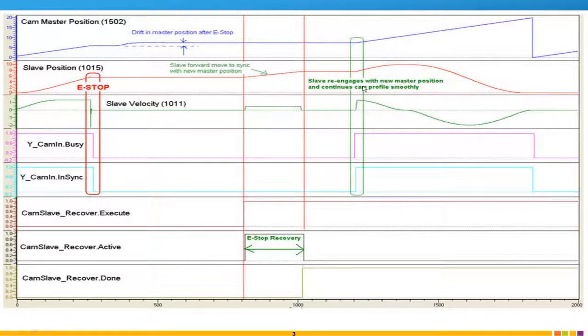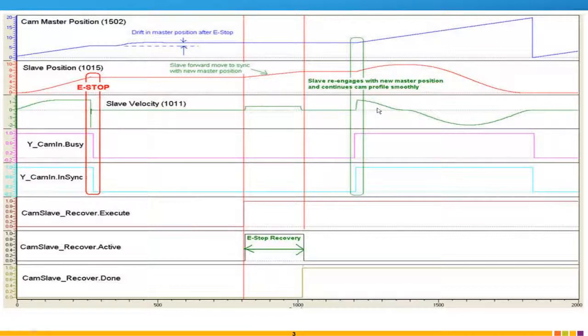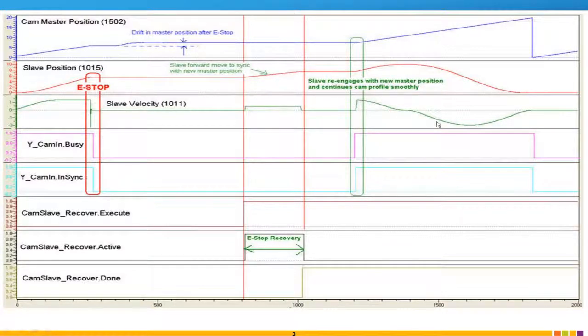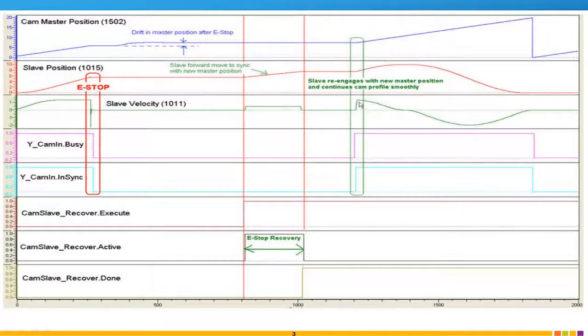So there's an example usage of the slave lookup. And I think what happens here, we are showing in the green section towards the right, when you have your master and slave realigned, at that point you'd be using a y cam in function block. But instead of using a normal engage position of zero, you would be using the master's current position as the engage position in immediate mode, because you're already in some portion of the way through the cycle.